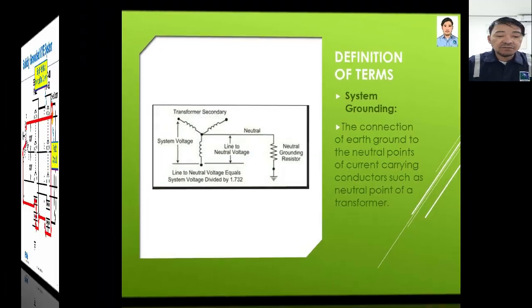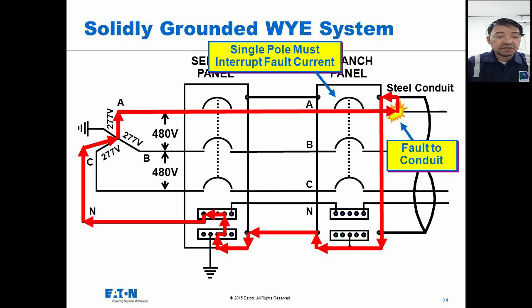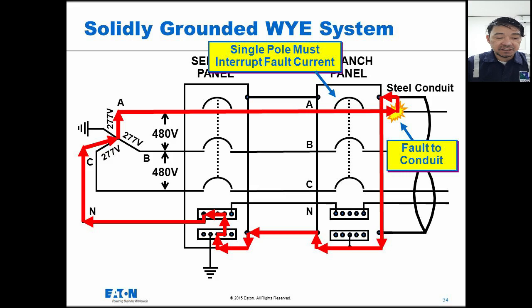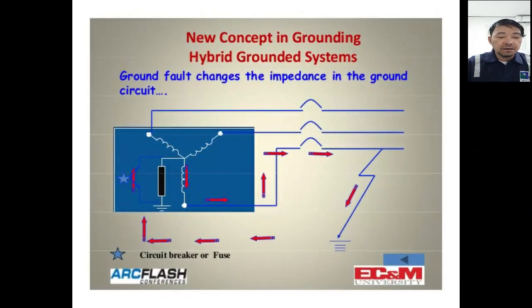For the solidly grounded system, the secondary of a transformer neutral, the X0 or wye point, is connected to ground. This configuration has the advantage of a phase-to-ground voltage but also has several disadvantages. The other one is an impedance grounded system, using impedance by means of a resistor or an inductor coil to limit the fault current to a very low level, typically from 1 to 10 amps.